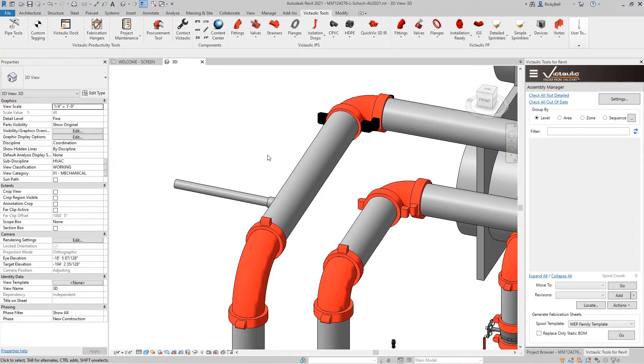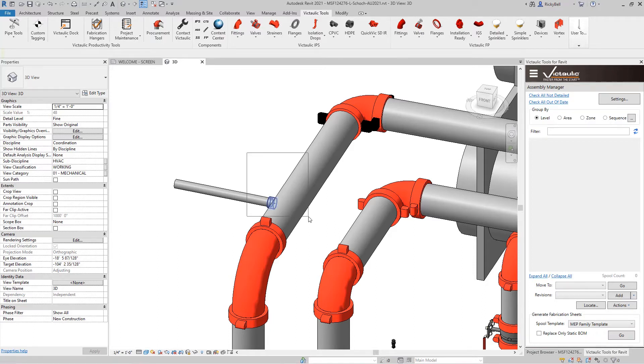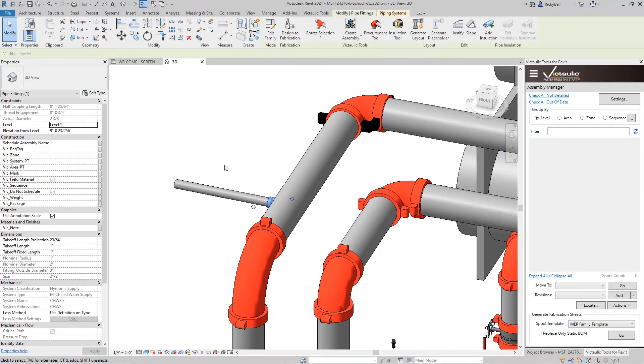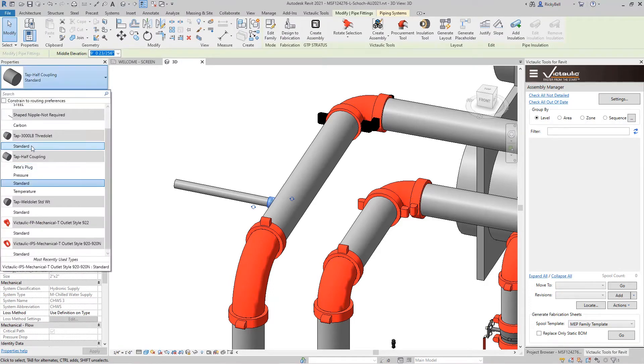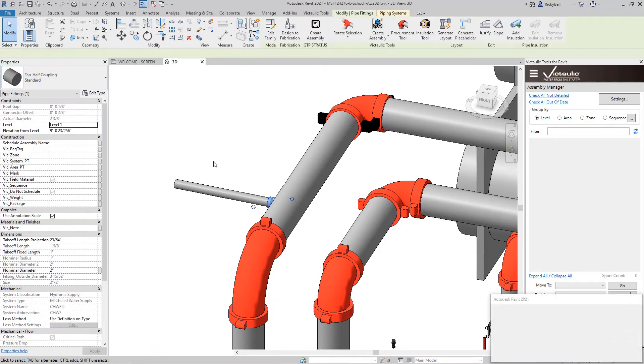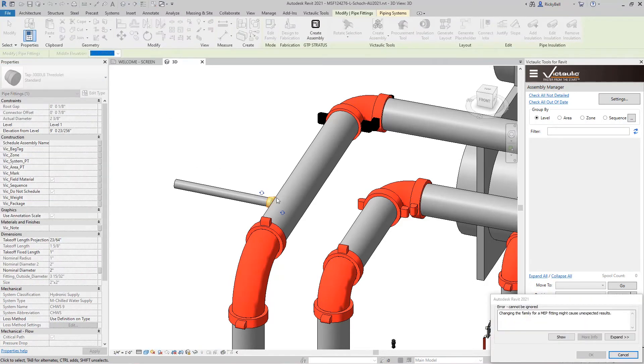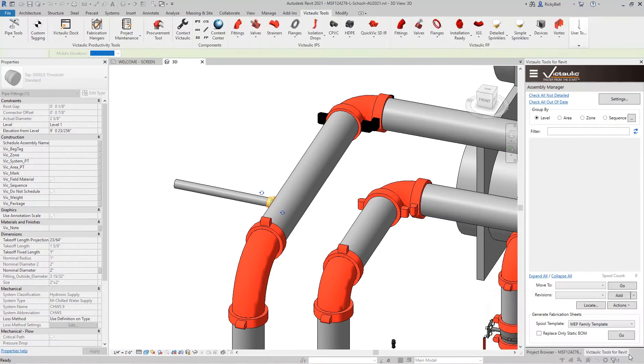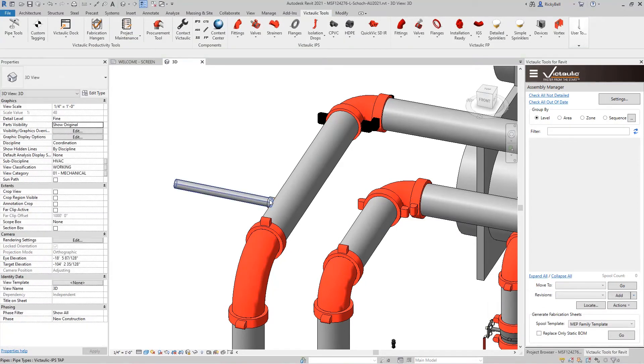So changing out a tap family on the fly within Revit is not actually possible. It does appear like you can do it. You can highlight it within your model. You can change it to a different type right here. It looks like it's going to go successfully. But then Revit comes back and gives you an error eventually just reverting your change.